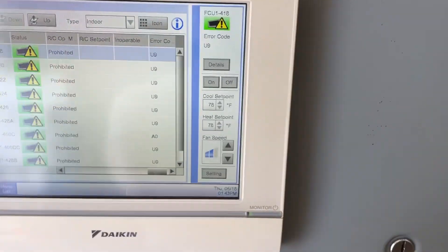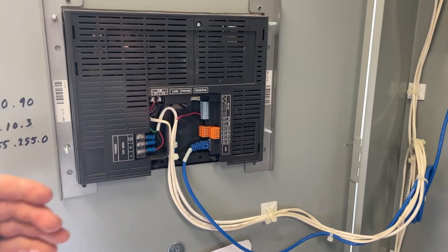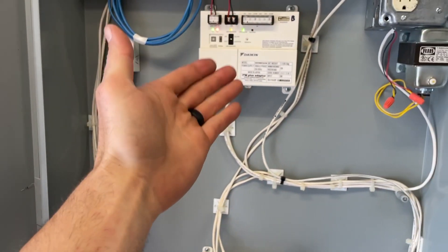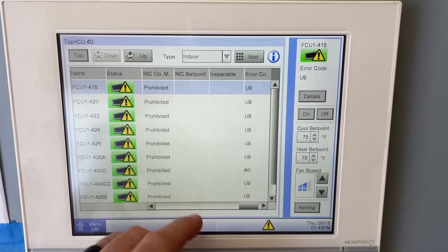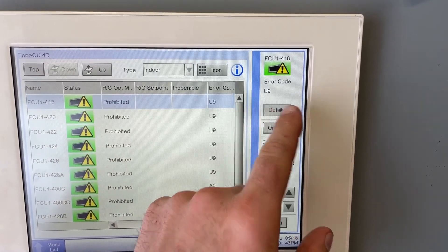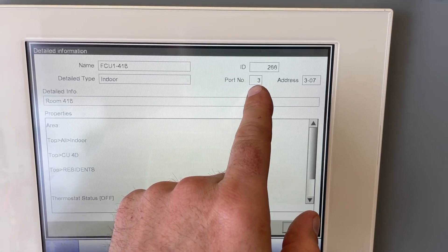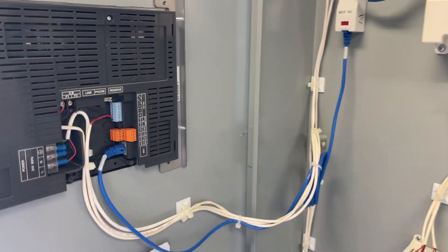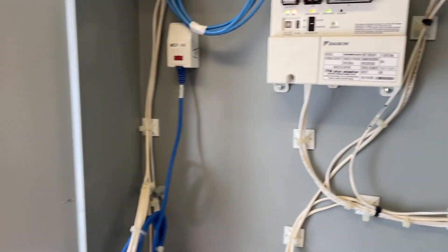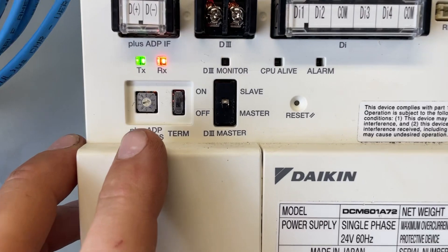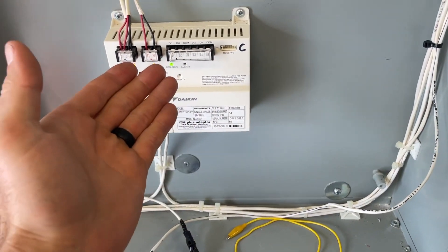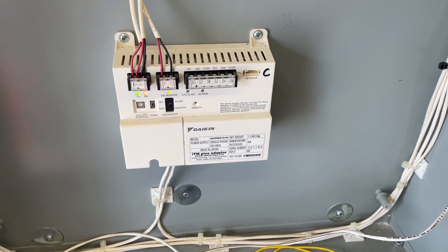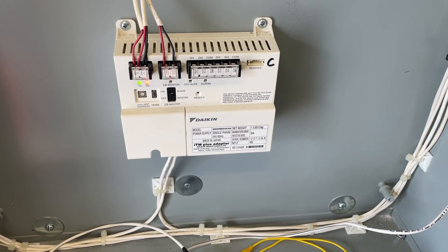This is a very, very big system out here. I've got a bunch of units on that adapter, and on that adapter. So how do we know which one to hook into? I'm going to go here and go to details, and you can see port three. This is port one, and that's always going to be port one because that's the central controller. Then I've got port two, and this down here is port three. So I'm going to get my F1, F2 hooked up, and then get on the computer in another location and take a look at this system.